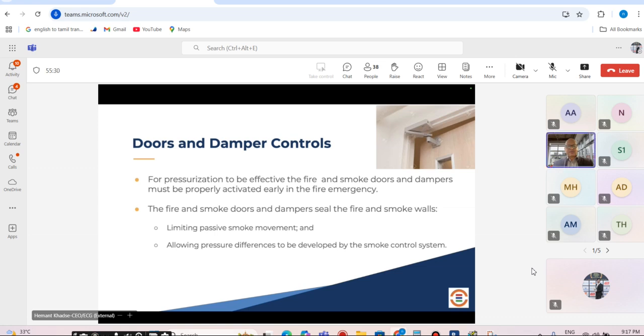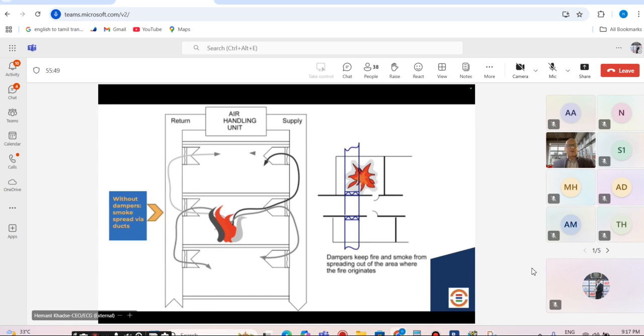It's again a part of a passive fire strategy, but essentially it is a design that has to be taken into consideration to limit smoke passage into the building horizontally or vertically. So when you design systems using the fire dampers, you'll have to see what's the logic that you are going to be building into your project, how your supply and return ducts are going to behave, how your supply becomes a return air duct, and how your exhaust is going to be activated, when it is going to be activated, how your adjoining floors are going to be behaving when it is going to be in exhaust mode for that particular fire zone.